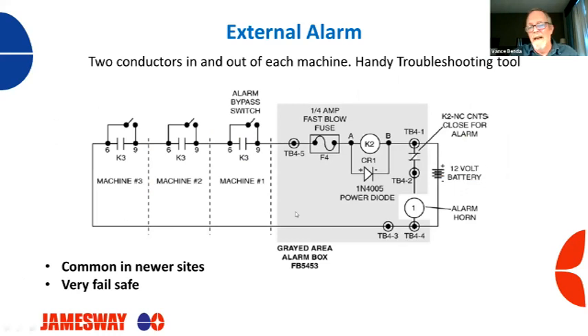Now this is a picture of an actual alarm loop. And again, I wanted to use the last slide to point out that this loop can be incredibly long at times. So whenever you start talking about this power supply over here, you have to realize that you have to supply enough power to make it out through that long loop, through all these relays, and back to this K2 relay to keep it latched. Because if this relay is unlatched, now these drawings, they have everything kind of sprawled out just so you can understand what you're doing. These contacts are actually contained inside this relay.